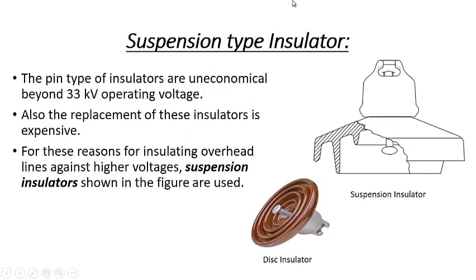Now the next one is the suspension insulator. Pin type insulators are uneconomical beyond 33 kV operating voltage. Also, replacement of this insulator is expensive, because if this 33 kV insulator is damaged, we have to replace it as a whole, and that will be very costly. But the suspension insulator will give us a little more reliability, and it will give us different options, and we'll see what these options are.